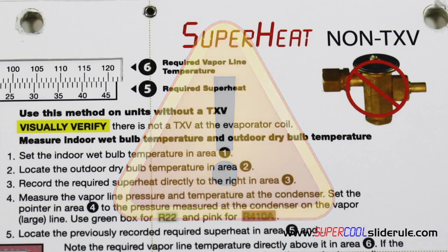A note of caution: many technicians are under the false impression that because an outdoor unit is printed with TXV in the system data plate, this somehow indicates that the unit is equipped with a TXV. All this actually indicates is a TXV is recommended for this unit. Many times, the installer installed a coil without a TXV to save money. So once again, I ask you to visually verify that there is not a TXV at the evap coil.